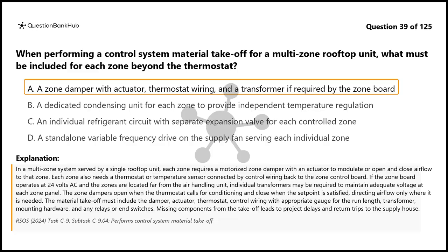The zone dampers open when the thermostat calls for conditioning and close when the setpoint is satisfied, directing airflow only where it is needed. The material takeoff must include the damper, actuator, thermostat, control wiring with appropriate gauge for the run length, transformer, mounting hardware, and any relays or end switches. Missing components from the takeoff lead to project delays and return trips to the supply house.